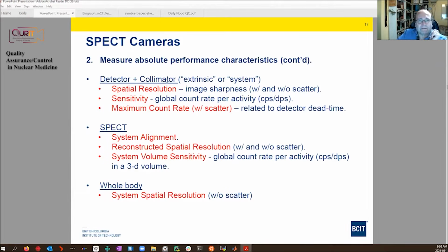Absolute performance, again, according to the NEMA protocol, they've got a section on measuring with the detector on. So the previous set was with the collimator off. If you just measure the properties of the detector by itself, they're called the intrinsic properties. If you measure them with the collimator on, they're called extrinsic or system values. And so we would measure resolution, we would measure sensitivity, which is sort of the global count rate per activity, and this will vary with the collimator. And one also can measure the maximum count rate with the collimator on with scatter. Won't go into why.